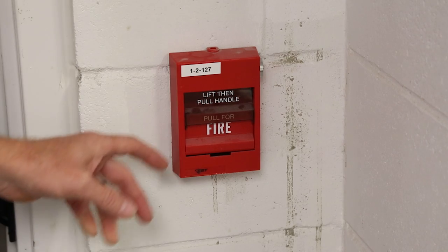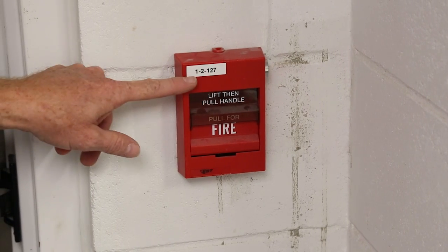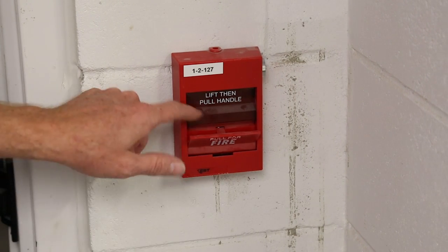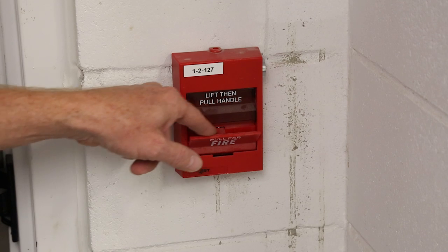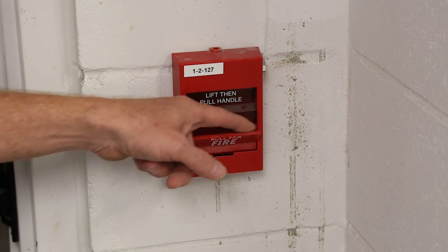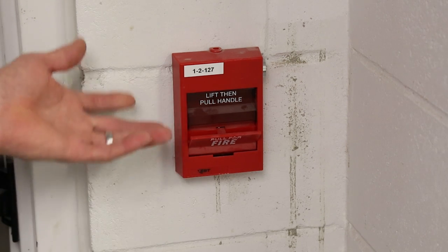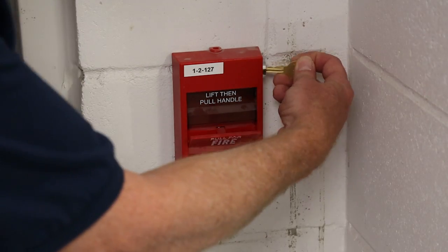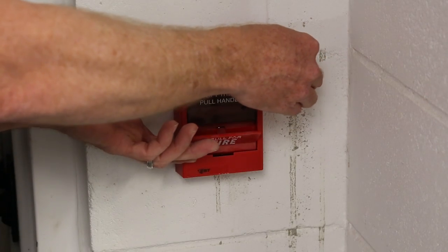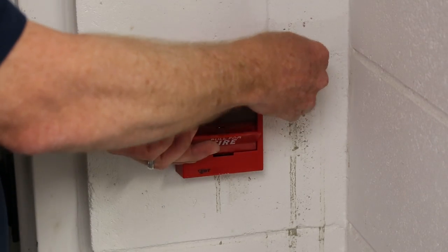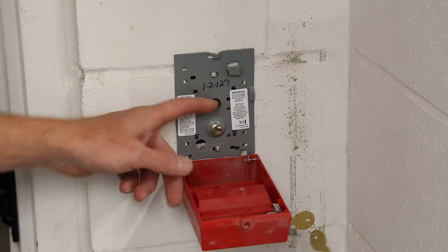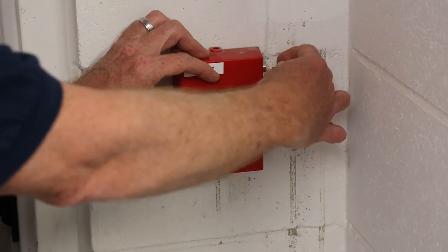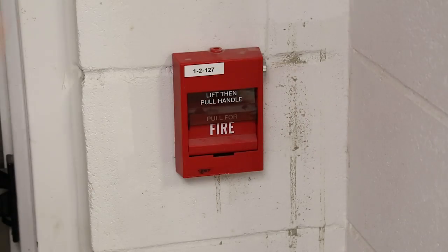All right, in the pull stations, basically we have the address label we're talking about right here for the device number. If the pull station is tripped, you'll basically see the handle sticking out like this. If the handle's sticking out like that, you can come and see it and it'll actually tell you the location of it. You can confirm the address. To reset it, remember the panel will not reset when a pull station is active. You have to reset the pull station first. Just stick the key in it, open it up, flip your switch back down, reorient the cover, shut it back up, and then go ahead and reset the panel.